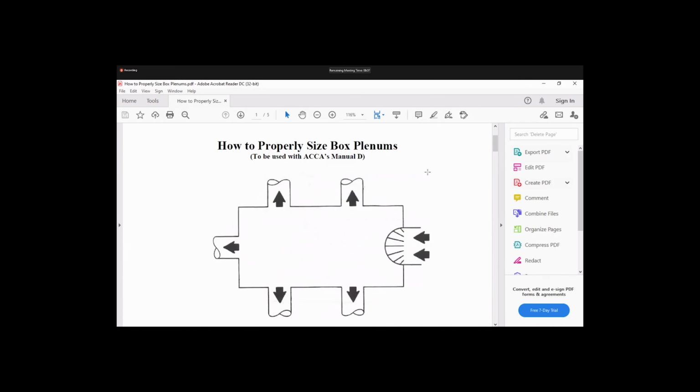Actually, what is a plenum box? The plenum box is made up of duct on the outside of the supply section of the equipment, like an AHU, FCU or any other unit. If there are a lot of branches, the length and fittings will increase if there is a long run of duct. So to reduce the fitting quantity, we use a plenum box, and also to divide the air evenly.